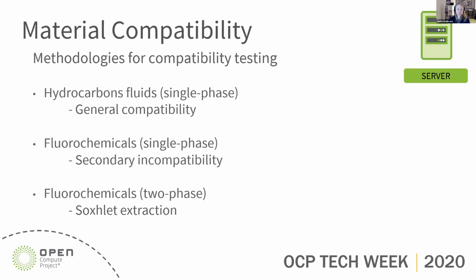If you're dealing with fluorochemicals in two-phase immersion, you can use Soxhlet extraction, where you're boiling off liquid and condensing it, exposing that to the material under test. This is to see if anything from the material under test is chemically reacting or leaching into the liquid itself, and then you analyze that in the end.